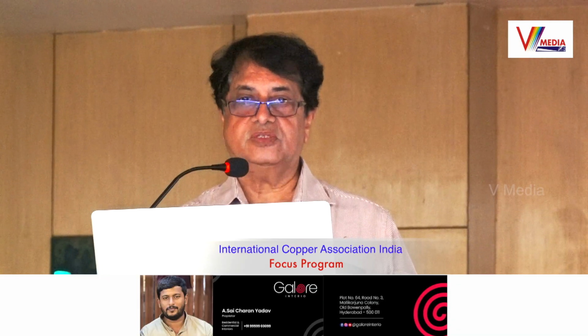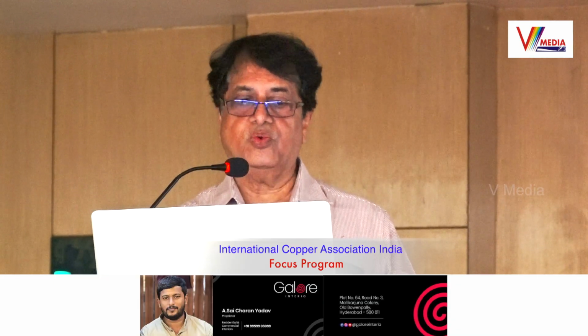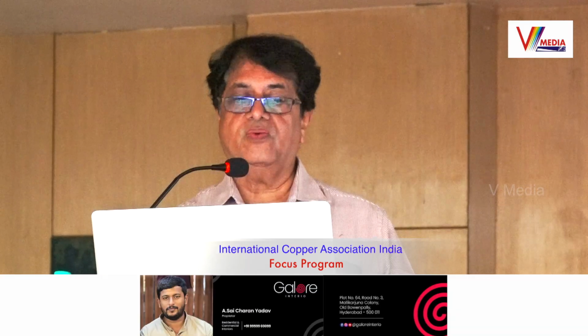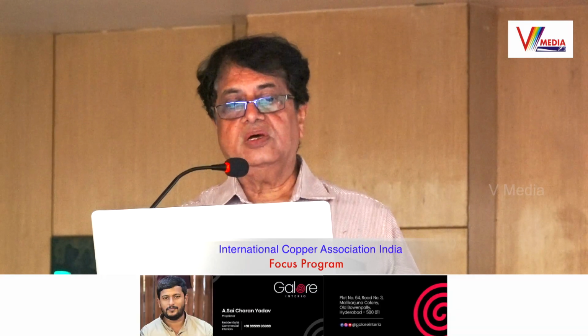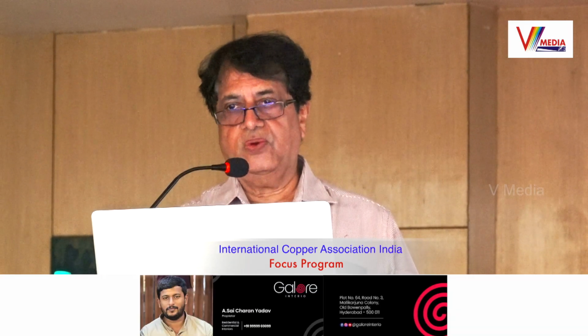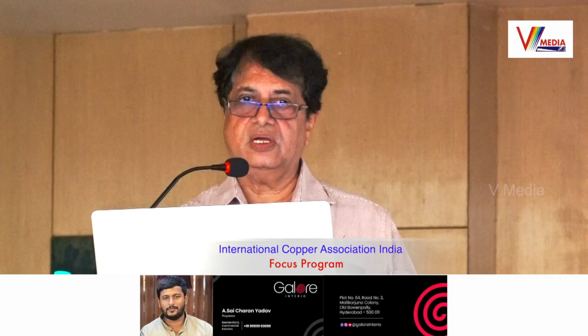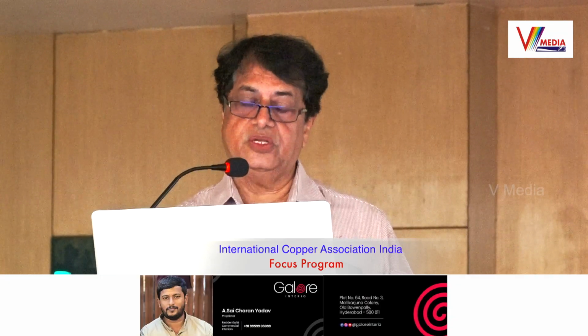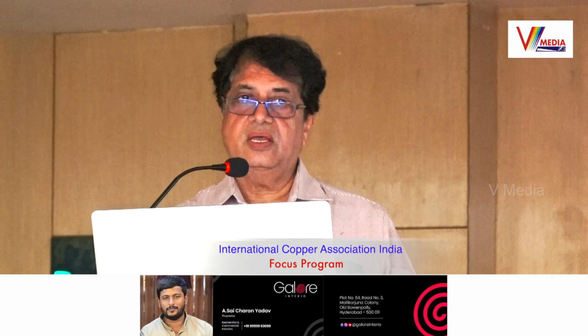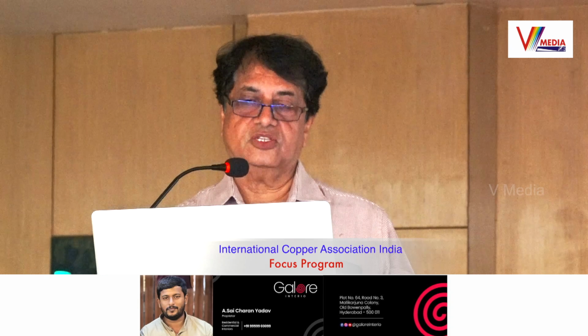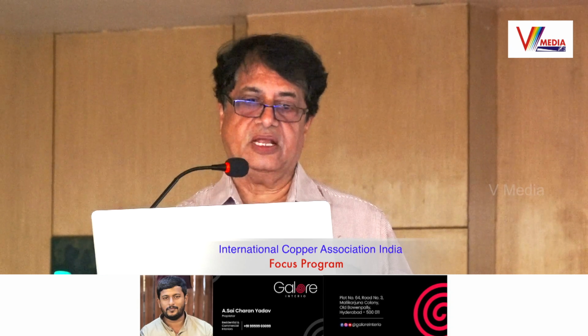So if such a condition is necessary, the architect will have to make provisions accordingly, so that the substation area is provided on the particular floor. If the transformer is to be installed on the upper floor, again some questions come into the picture: in future there could be some fault in the transformer and they may have to replace that transformer.